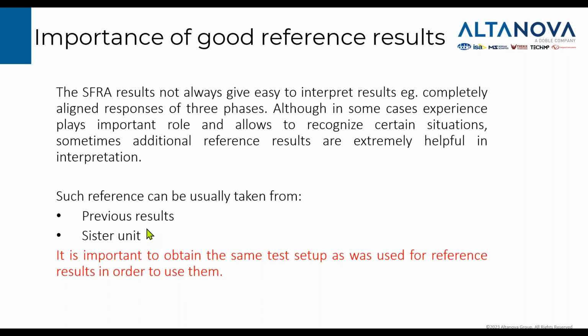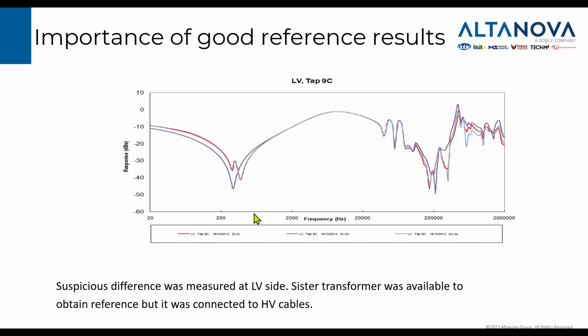Or we might also have a sister transformer, which has the same design, and we might be able to test it, or we already have test results for that one, so that we can compare with this one, because it is supposed to give very similar test results. So that's why it is important to obtain the same test setup as was used for reference results. Here we have an example of reference taken from a sister transformer. This transformer was tested in one of the locations in the Middle East.